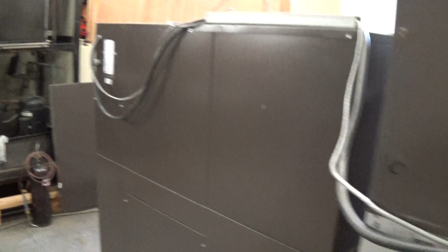Phase rotation is important. The fans are not three-phase, so you can't go by those. So when you turn the chiller system on, after you get glycol in the system, of course, the default indicators here are suction pressure and PSI. So as soon as you hear a compressor come on, those should be dropping down fairly quickly. If not, it's probably out of phase.